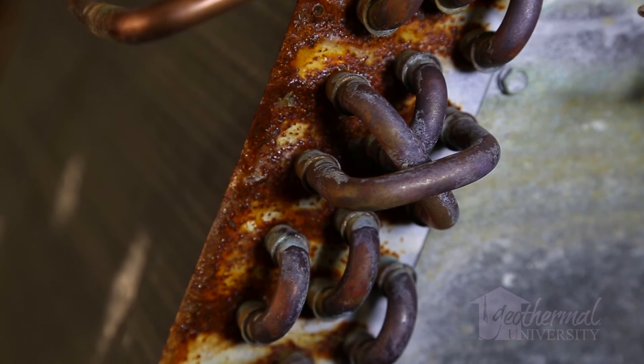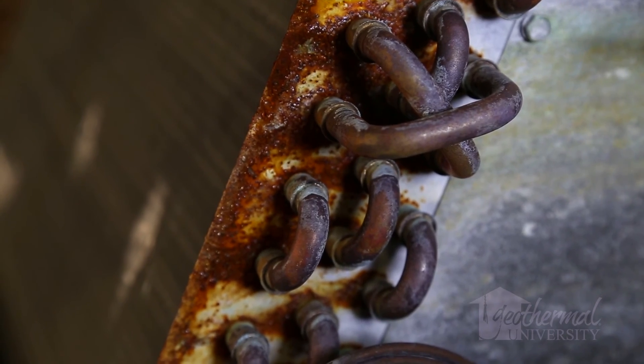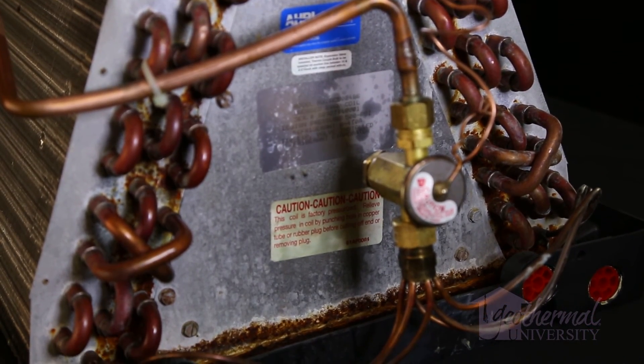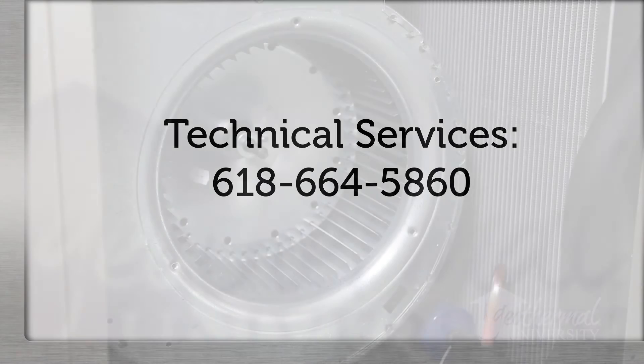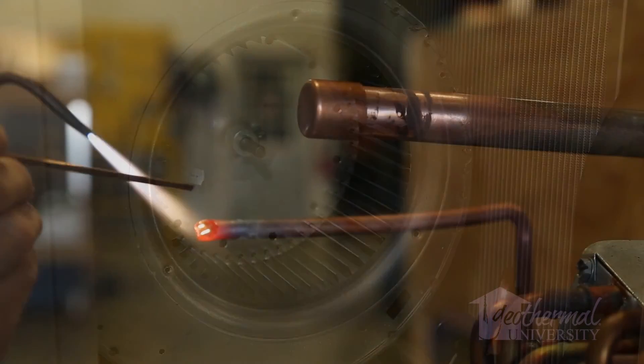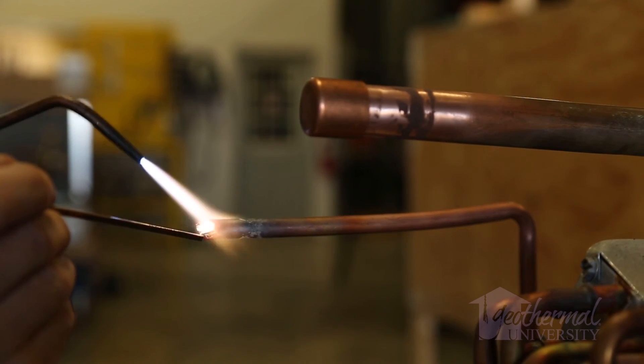Some of the corrosion type leaks discussed in this video are very difficult to repair. Before repairing a coil that has failed because of corrosion, we recommend calling tech support for more information. Many coils such as microchannel can be repaired. Remember when brazing on a refrigerant system to use a nitrogen flow of 2 to 3 psi to prevent internal scaling.